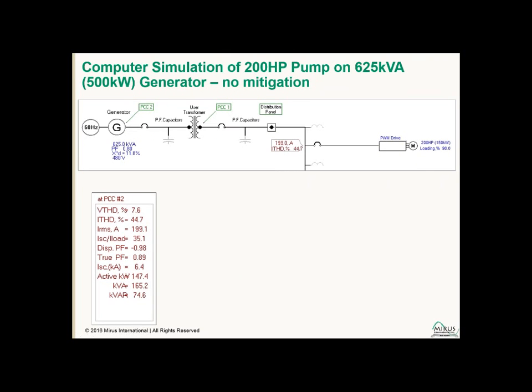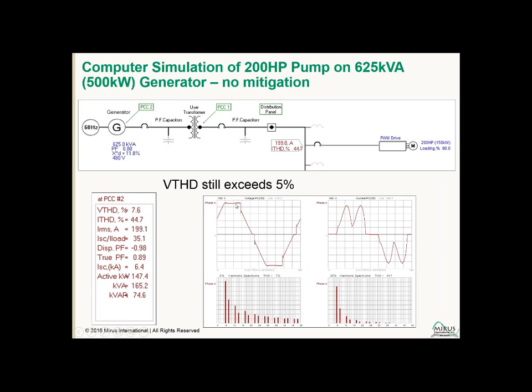So when we came to site, they had already installed a 500 kilowatt generator. This first simulation, I'm showing no mitigation. There was an AC line reactor, I'll show that next. But without any line reactor, on a 500 kilowatt generator, we're at 7.6% voltage distortion, 45% current distortion. You can see the voltage is still pretty severely flat topped. A fair bit of distortion, much sharper pulses in the current.